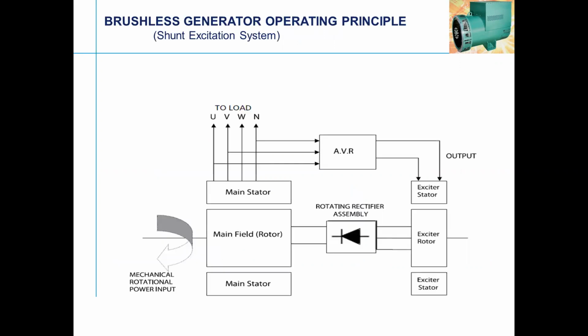How can it be done? This is a shunt generator. If you can see this, these are the outgoing leads U, V, W, N, this is a rotor winding, this is a stator, and this is a rotating rectifier assembly, with the exciter stator and exciter rotor. And this is the part that couples with a prime mover, an engine or a steam turbine, whichever it is. The exciter plays an important role in feeding the voltage to the main rotor. This is the winding we have seen in the main rotor. It feeds the voltage through the RRA, which converts AC to DC and feeds the main rotor. For feeding the exciter rotor, some potential, that is voltage, is required, and that is fed from the exciter.